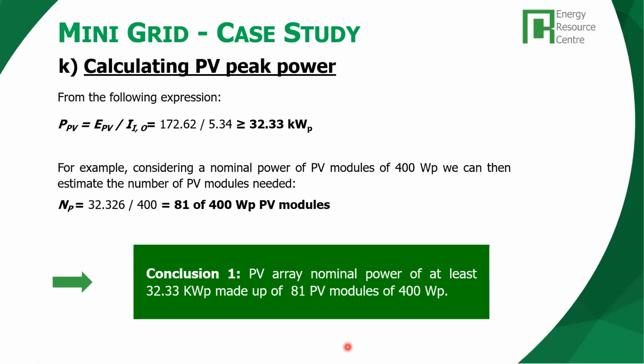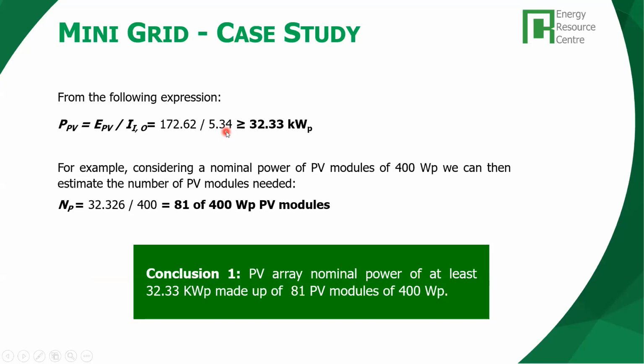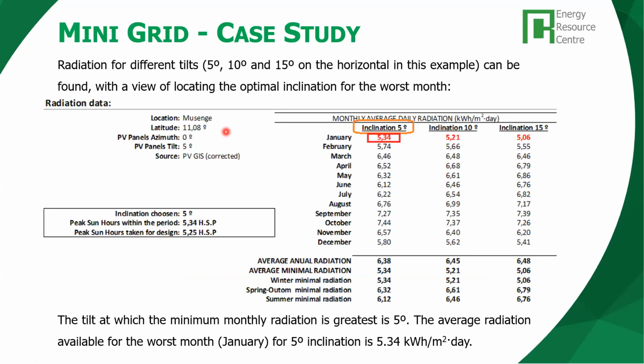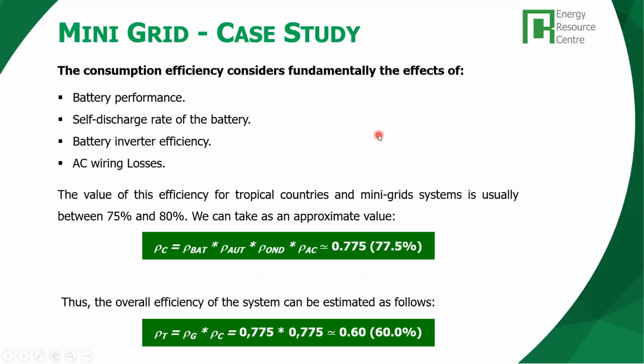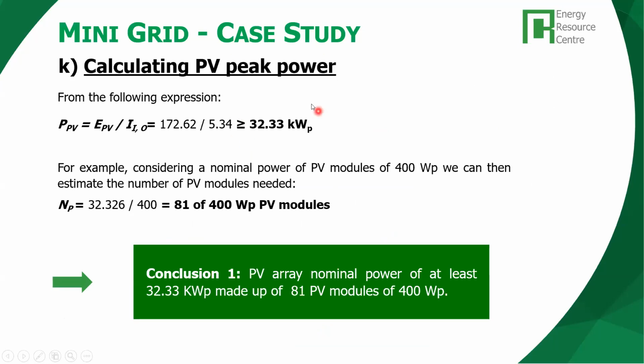Okay, so if you remember our calculations, we need to generate 172.6 kilowatt hour per day. We have a level of sun peak hours in the worst condition, which is January, of 5.34. 5.34 is the sun peak hour. So we get a sizing of the PV system in the range of 32.3 kilowatt peak for this mini grid. Okay. If we look at PV modules of 400 watt peak each, we need roughly 81 modules.